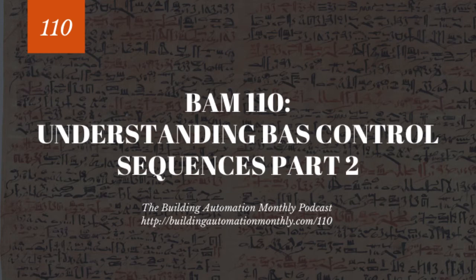Because what happens is you'll hear a lot of folks who say, when my air handler starts up, it trips on static safety. Well, a lot of programs these days will actually go and take their VAV boxes and program them to be tied to the air handler. So when the air handler is enabled, the VAV box comes on. Here's the problem with that. These programs will often close the VAV dampers, because what these programmers or the sequence writers or whoever's coming up with this isn't realizing is that when you close those dampers, they have a 90-second stroke time.